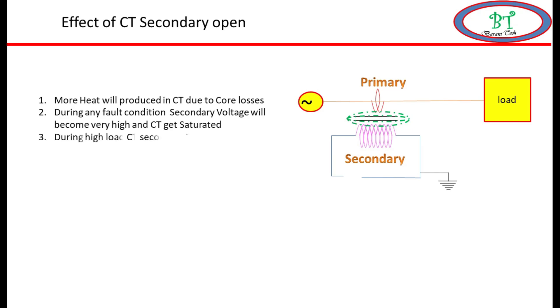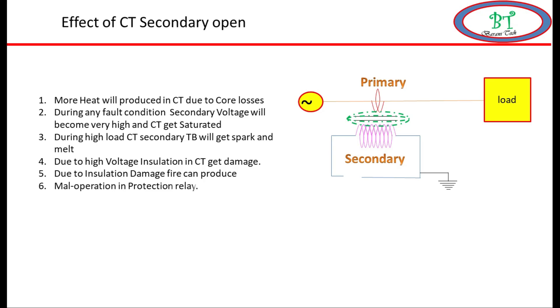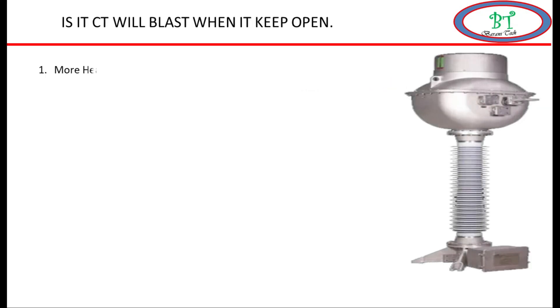During high load, the CT secondary TB will get spark and melt. Due to high voltage, the insulation in CT gets damaged. Due to insulation damage, fire can be produced. And also due to this CT open in the secondary, it may mal-operate the protection relay.